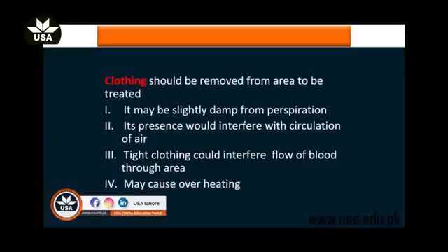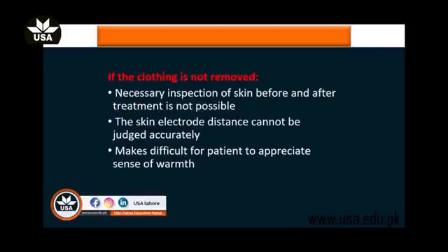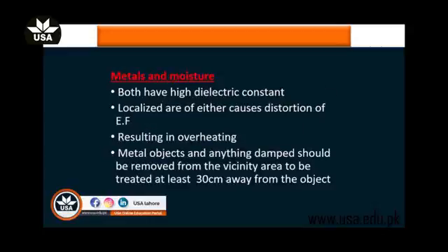Actually, it may be slightly damp from perspiration, and its presence would interfere with the circulation of the air as well. Tight clothing could interfere with the flow of fluid through the area and may cause overheating. If the clothing is not removed, necessary inspection of the skin before and after the treatment is not possible. The skin electrode distance can't be judged accurately, and it makes it difficult for the patient to appreciate the sense of warmth.